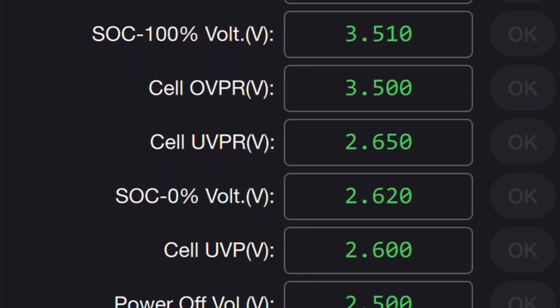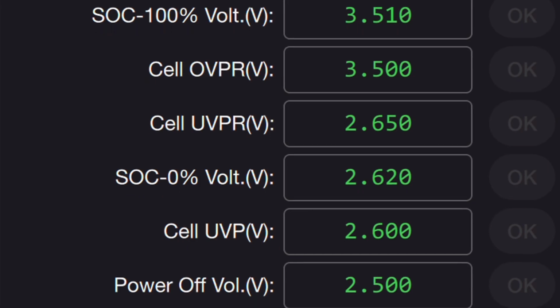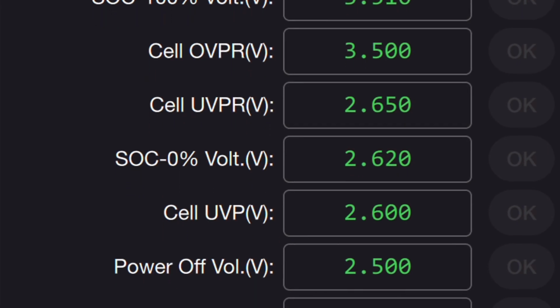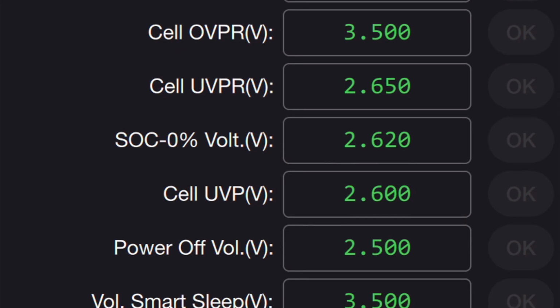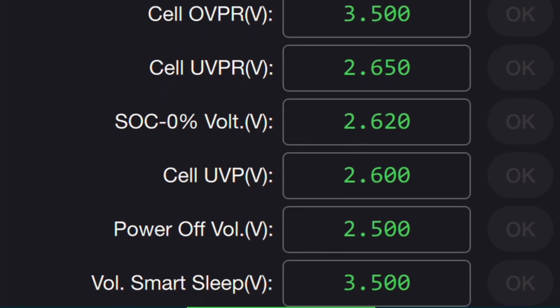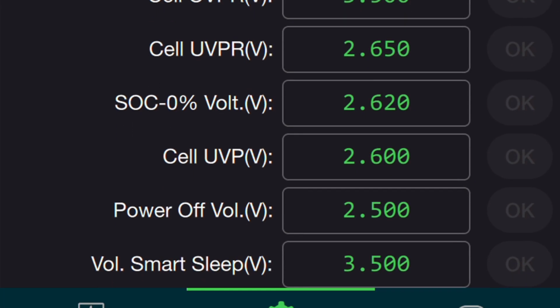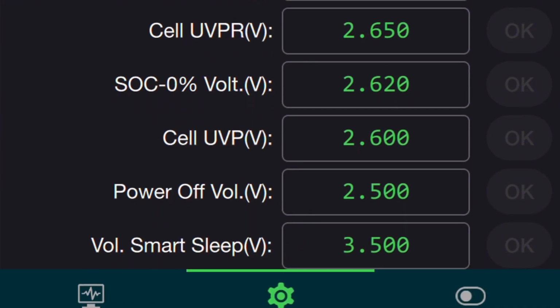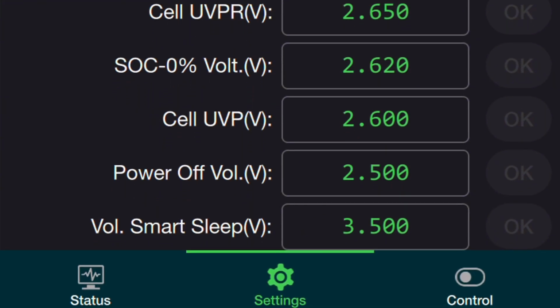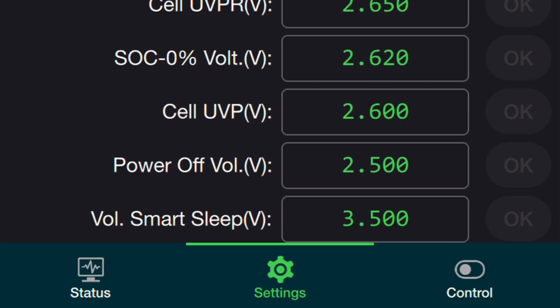Overvolt protection restart: when it drops to 3.51, it'll come back on if it's been shut off at the high overvolt protection. Cell undervolt protection at 2.65 will turn back on if it was shut off due to undervolt protection. And if it gets down to 2.62 volts per cell, it will automatically reset the pack to 0%, allowing you to bottom balance as opposed to top balance.